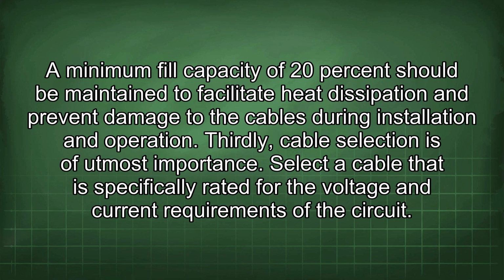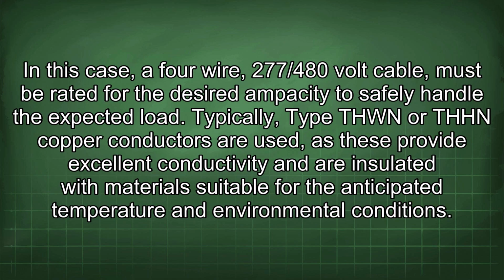Thirdly, cable selection is of utmost importance. Select a cable that is specifically rated for the voltage and current requirements of the circuit. In this case, a 4-wire 277/480 volt cable must be rated for the desired ampacity to safely handle the expected load. Typically, type THWN or THHN copper conductors are used, as these provide excellent conductivity and are insulated with materials suitable for the anticipated temperature and environmental conditions.